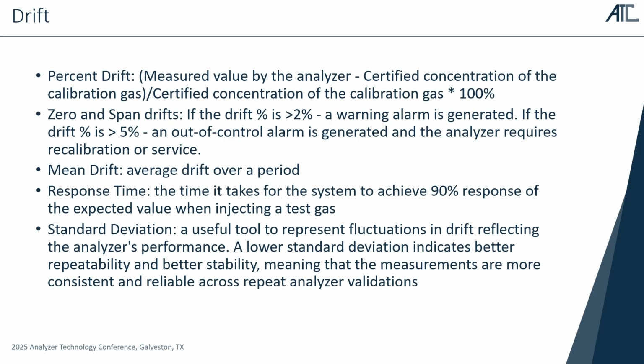So for these validations, you typically need to run them daily, and then you also have to do a root cause analysis if you failed, and then you can backfill the data as well. There's a lot of intricacies about these regulations that we can't cover in a simple session like this. But drift would be one of the main KPIs, and then a bunch of other KPIs are generated, like mean drift, response time, standard deviation. A lower standard deviation represents better stability, versus a high standard deviation, where you'd investigate why your validations are jumping all over.